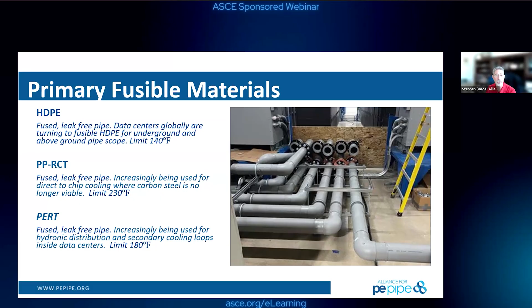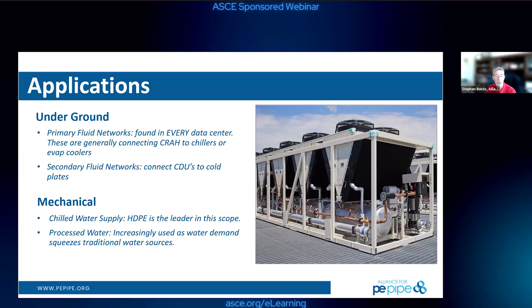Like I said, on the underground side, every data center needs these. You've got to connect piping to chillers, bring water to them, and you're going to have secondary systems that connect to the CDUs, as we talked about. Then on the mechanical side, that's kind of the differentiator of this inside and outside the building. You're going to have chilled water and heated water, so each material is going to play a different role in that.